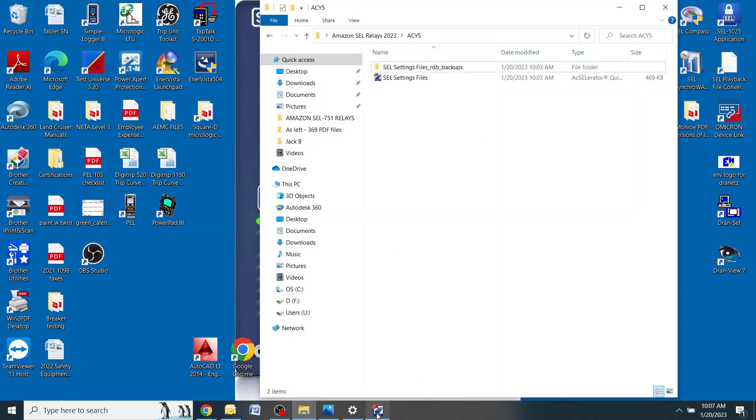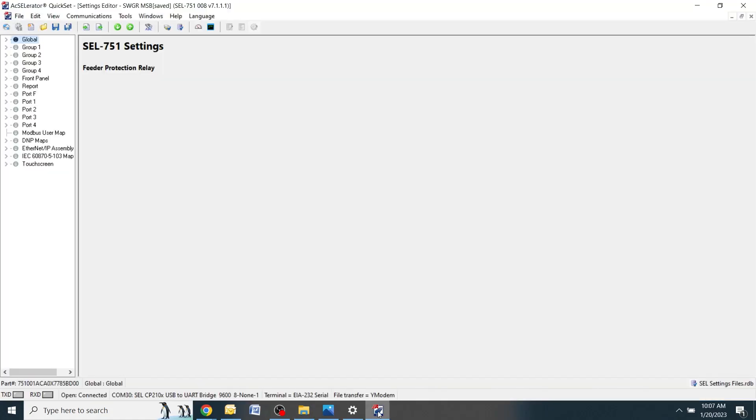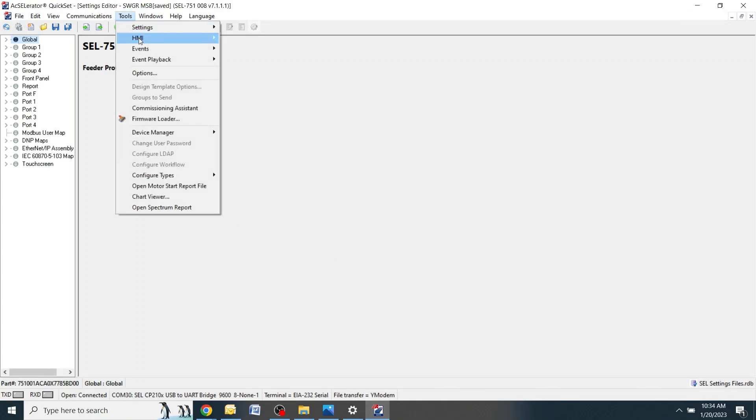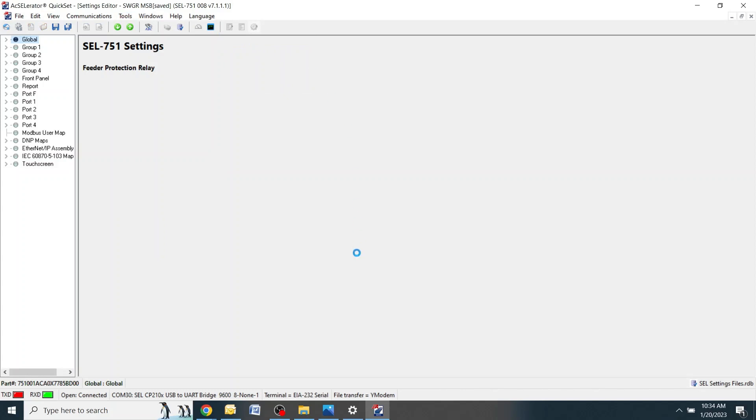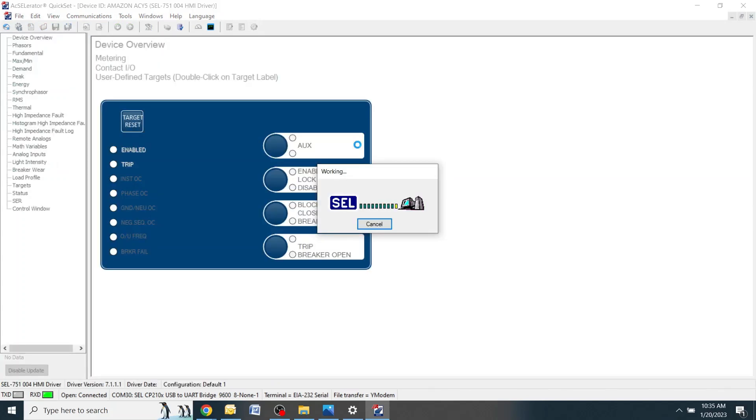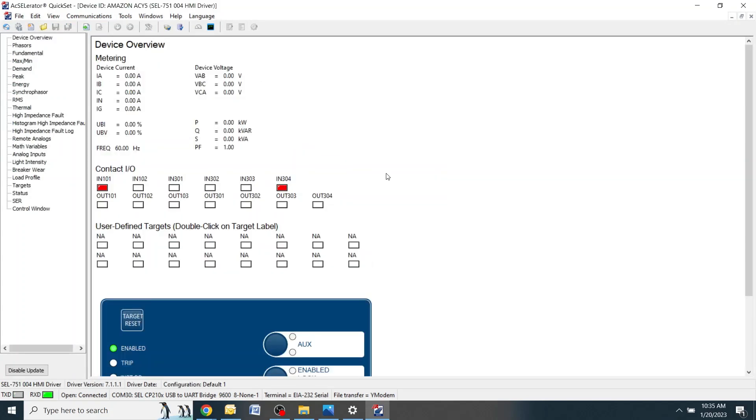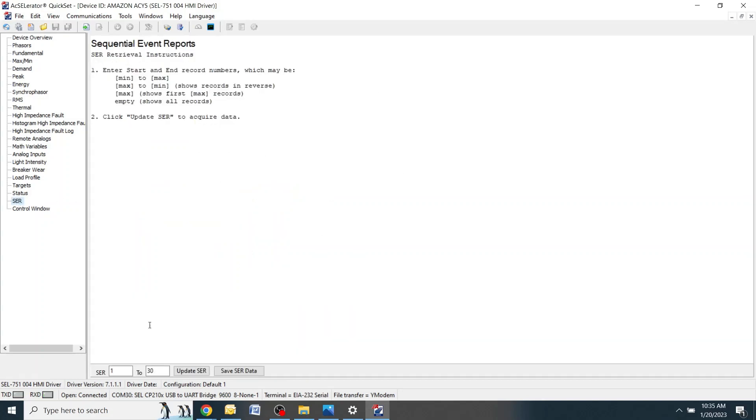Go back to the Accelerator QuickSet screen. To access the SER files, go up top to tools and click HMI. This screen might take a few seconds to load. Once you're in the HMI screen, go over onto the left hand side, double click where it says SER. Down at the bottom you'll see it has one to 30 and there are no SER events listed here. Change this number to 100 and click update SER.